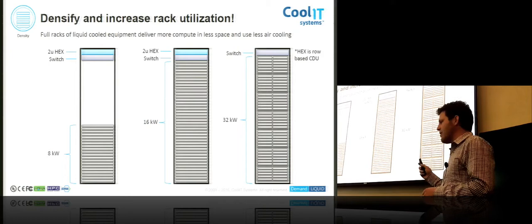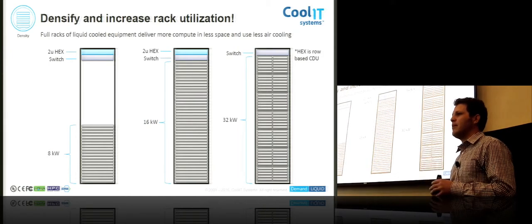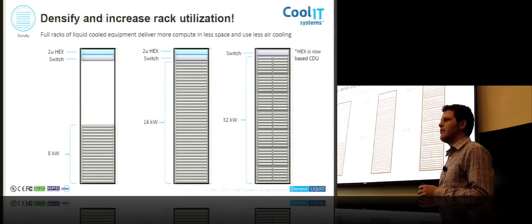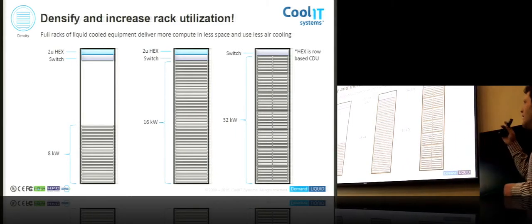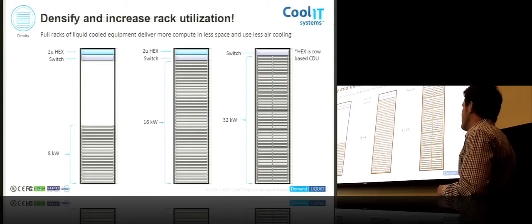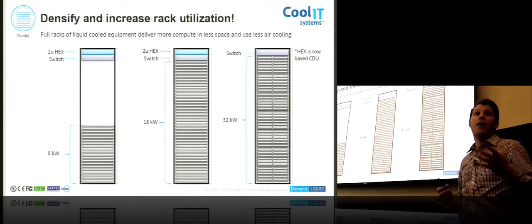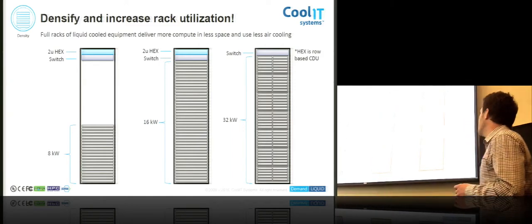So what happens here is we can evacuate with cold plates about 70%, depends if there's GPU involved, maybe up to 80% of the load, out through the warm water and up to a more passive cooling unit on the roof, the side, whatever. And allow that air cooling to pick up essentially what it was before. So this does require that you have the power available in the room to boost up your compute.